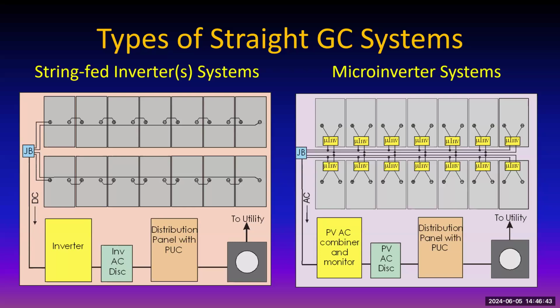So each of these strings is combined. The outputs of every string are carried on down to the combiner. So here you'd have 4 wires plus a ground coming down to the combiner, where the outputs of the 2 strings are combined together. So if you've got 12 amps and 10 amps, you get 22 amps at the output of the combiner. Okay, and then it goes to a disconnect. And if you turn off the disconnect, then all those microinverters think the utility's gone away and they shut off. Then it's connected to the utility through the distribution panel, and that's the system.